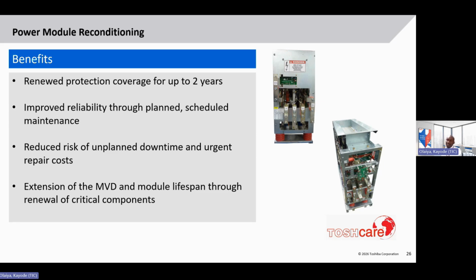And finally, most importantly, this service helps to extend the life of both the drive and the power module through renewal of critical components. Replacing these components with new ones is a way of also resetting the life of that power module, which in general is 20 years, even though we have modules older than that still operating today.